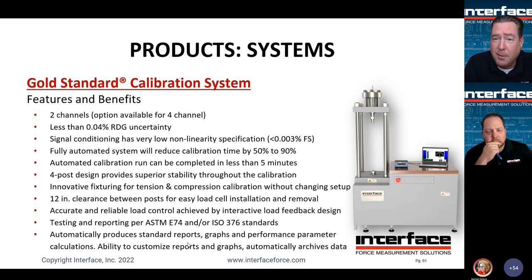As Brian mentioned earlier, I won't touch too much on this, but this is the top of the line in terms of what we offer for metrology systems on the system level. And this would be a complete calibration load frame. These are available in standard capacities of 55,000 pounds and 100,000 pounds. And we have two different standard heights available. So if you don't need a super long load string, there is a shorter height version available and a taller version available with various working heights.